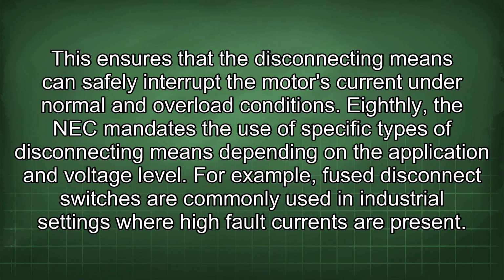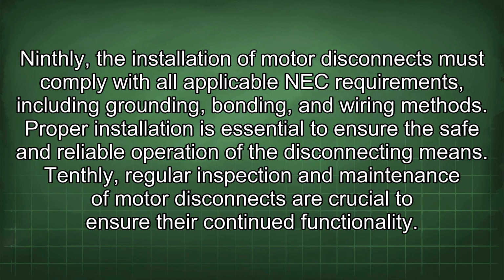Eighthly, the NEC mandates the use of specific types of disconnecting means depending on the application and voltage level. For example, fused disconnect switches are commonly used in industrial settings where high fault currents are present. Ninthly, the installation of motor disconnects must comply with all applicable NEC requirements, including grounding, bonding, and wiring methods. Proper installation is essential to ensure the safe and reliable operation of the disconnecting means.